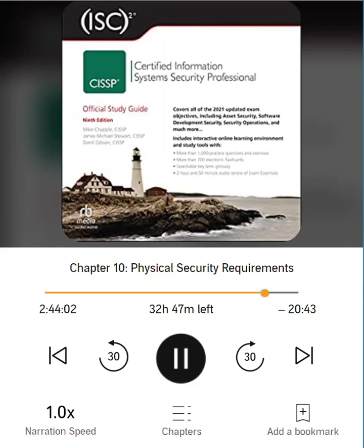A computer room does not need to be optimized for human workers to be efficient and secure. A server room would be more secure with a non-water fire suppressant system. It would protect against damage caused by water suppressant. A server room should have humidity maintained between 20 and 80% relative humidity and maintain a temperature between 59 and 89.6 degrees Fahrenheit.